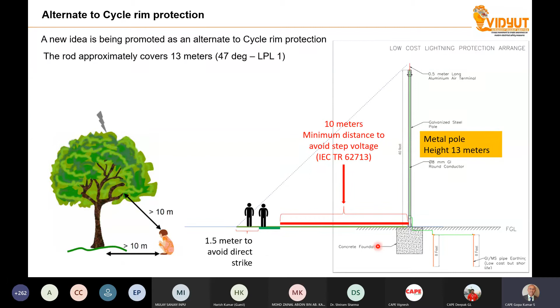So if we look from the actual view, this is the rod. The orange color is the claimed protected area. The first 10 meters you cannot go to because of the step potential. Then you have about 1.5 meters, which is actually protected. The last orange place you cannot use because you will get a direct hit. So if these systems are installed, people during lightning should run towards this particular rod. Then they have to find out where this 1.5 meter is and stand on it. If you go closer, there is a problem. So such dangerous systems are proposed across India.